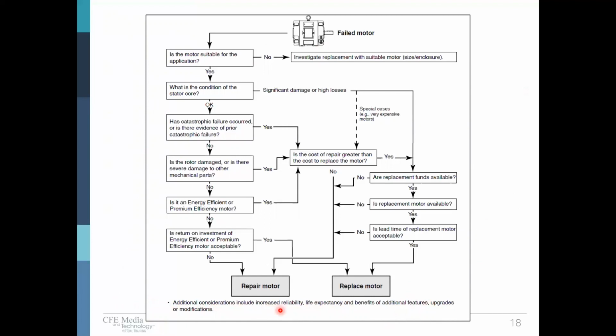Reliability: we want a new motor, maybe we want to put some type of shaft seal on it to allow it to last longer in a water spray environment. If we're going to repair it, we want to do the same thing. We want to put some type of additional shaft seal on it. So those are other considerations. So we've got this motor now, we're going to move way down, and we're going to say, suitable for the application? Yes, it is.